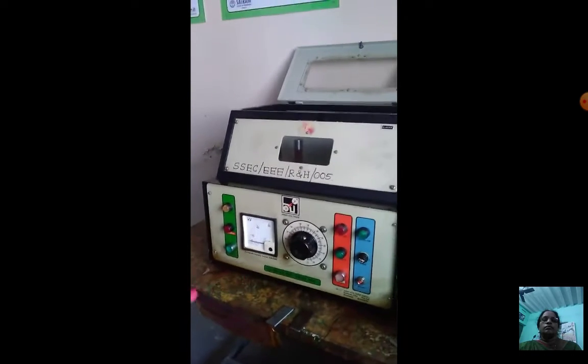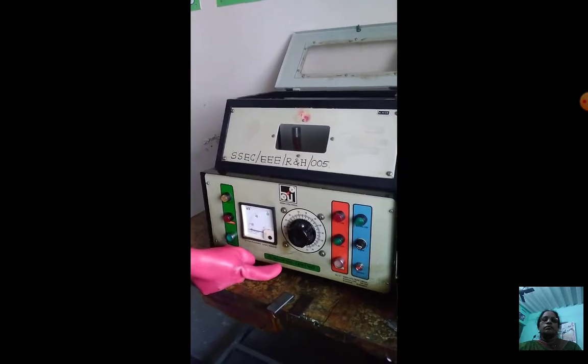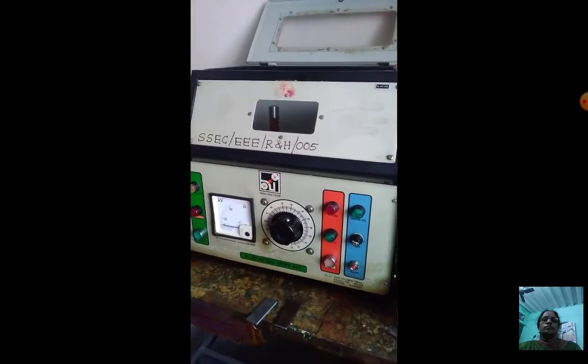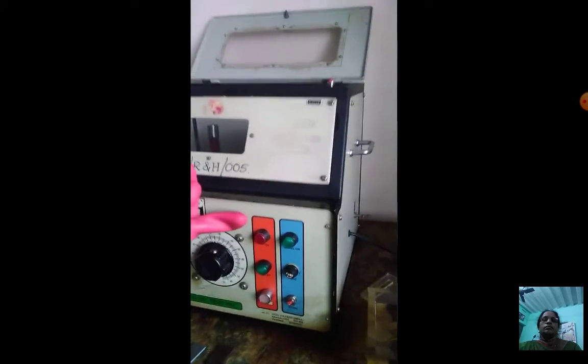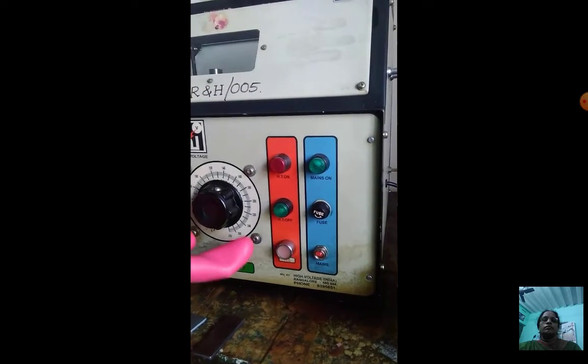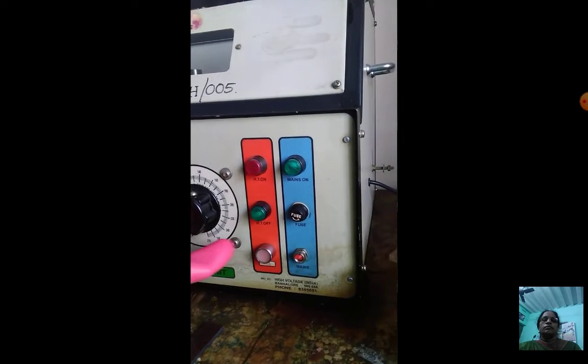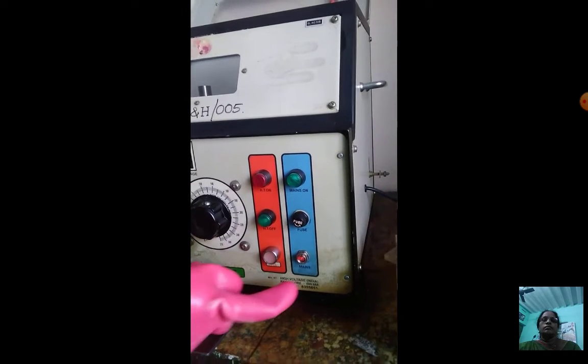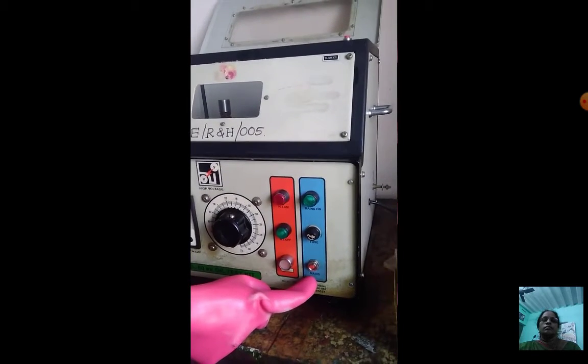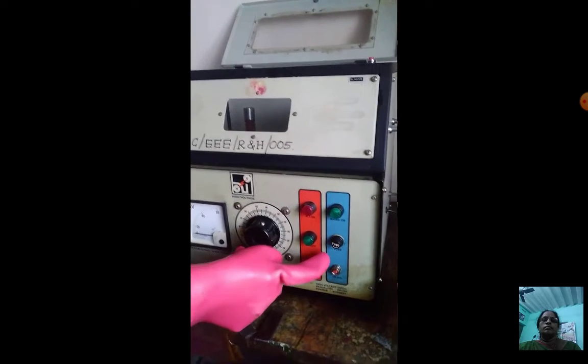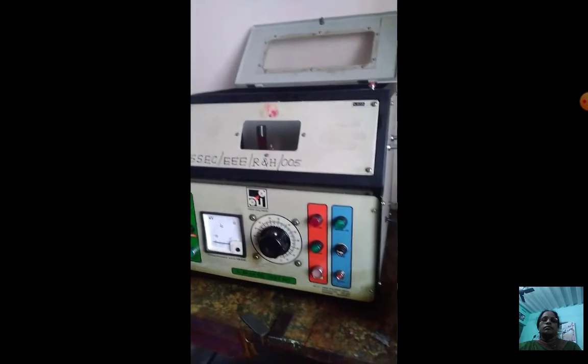The kit total is nothing but a 0 to 60 kV oil test kit only. So this is the high tension on indicating lamp. This is the high tension off indicating lamp. This is the high tension push button switch. This is the toggle switch for mains on. This is the fuse. This is the main on indicating lamp. This is the test cell.